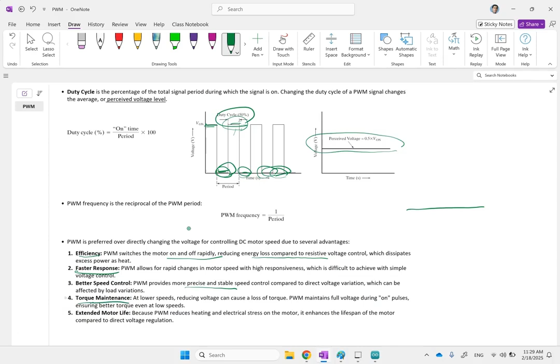The other benefit is torque maintenance. When you're at lower speeds or higher torques, if you reduce the voltage, it can cause a lot of loss of torque. Remember, voltage, torque, and omega are related, so if you bring down the voltage, you lose a lot of torque. But with PWM, you don't change the maximum voltage, you just change the width called the duty cycle, so you can better keep the torque at lower omegas.